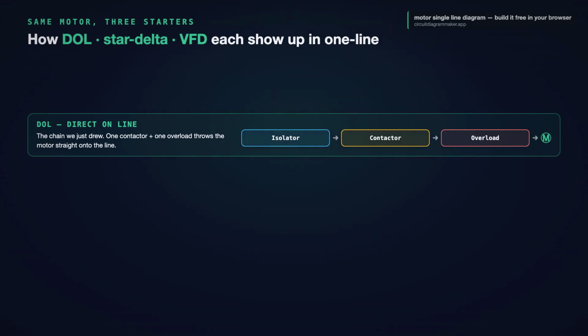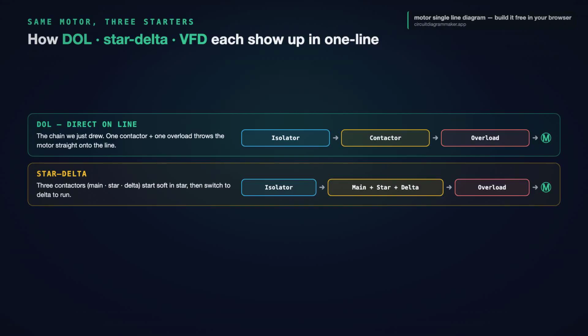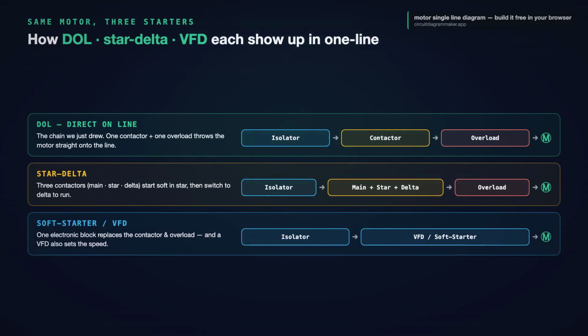Direct online. The chain we just drew is the simplest, one contactor, one overload, and the motor is thrown straight onto the full supply. Star-delta swaps that single contactor for 3, a main, a star, and a delta contactor, to start the motor softly in star, then switch it to delta to run. On the one line, you draw the 3 contactors so the reader knows. And a soft starter or a VFD replaces the contactor and overload with a single electronic block. And a VFD also sets the motor's speed. Same motor, same supply, but the starter block on the drawing tells you exactly which method is in that panel.